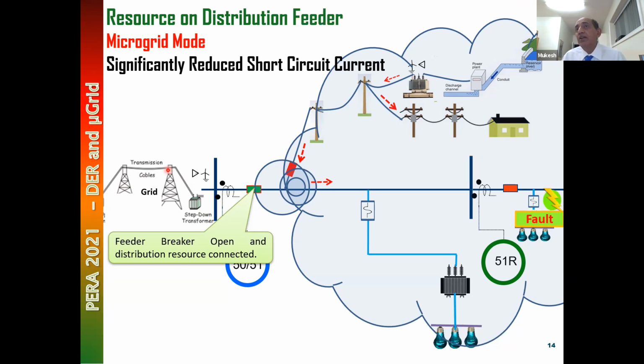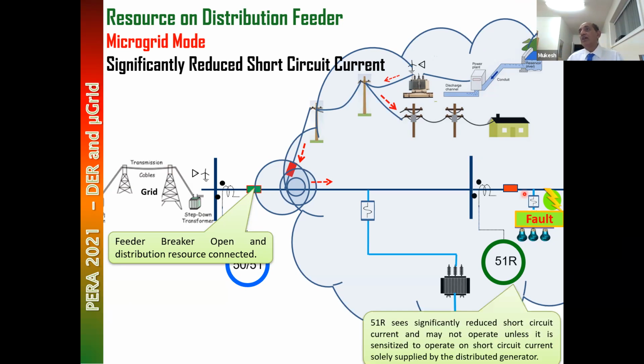But with this breaker open, the short circuit current seen by this protection is significantly low. The protection 51R has to operate correctly when it is closed, operating in parallel, and also has to work correctly when the grid is isolated. So it has to work in both modes.